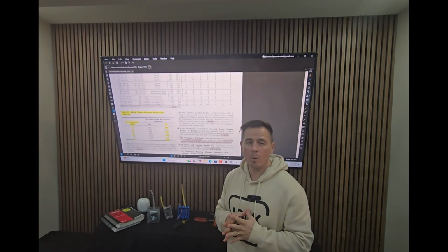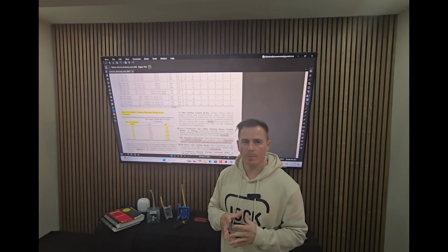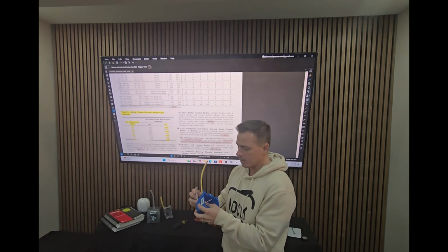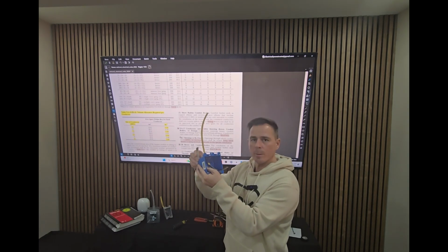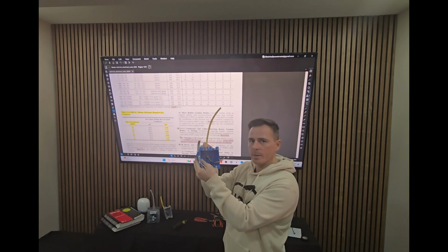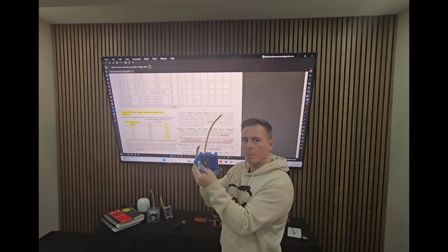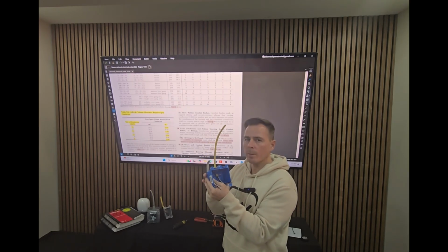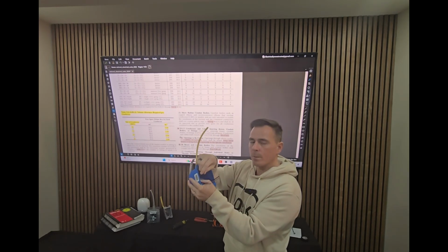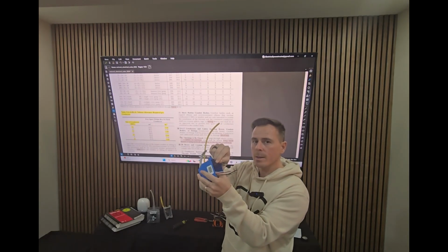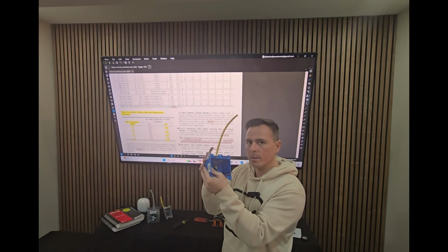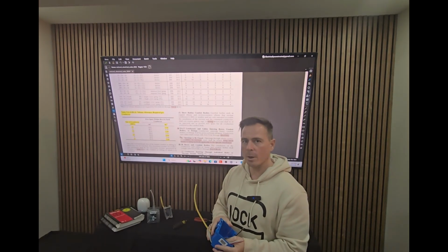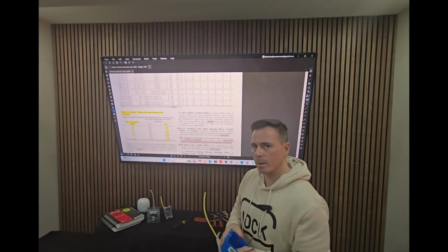All right, guys, I'm going to give you a quick code question before we finish up here. If I have a box like this and I have a 14/3 running into it and I got a 12/2 running into it, how much volume will these wires add to the box? We haven't gone over it yet, but I'm going to let you know right now: on the 14/3, the equipment grounding conductor does not count towards the volume of this box. That's the only clue I'm going to give you right now. I'm going to give you a minute to try to add this up, get your answer, and then we'll go through it.